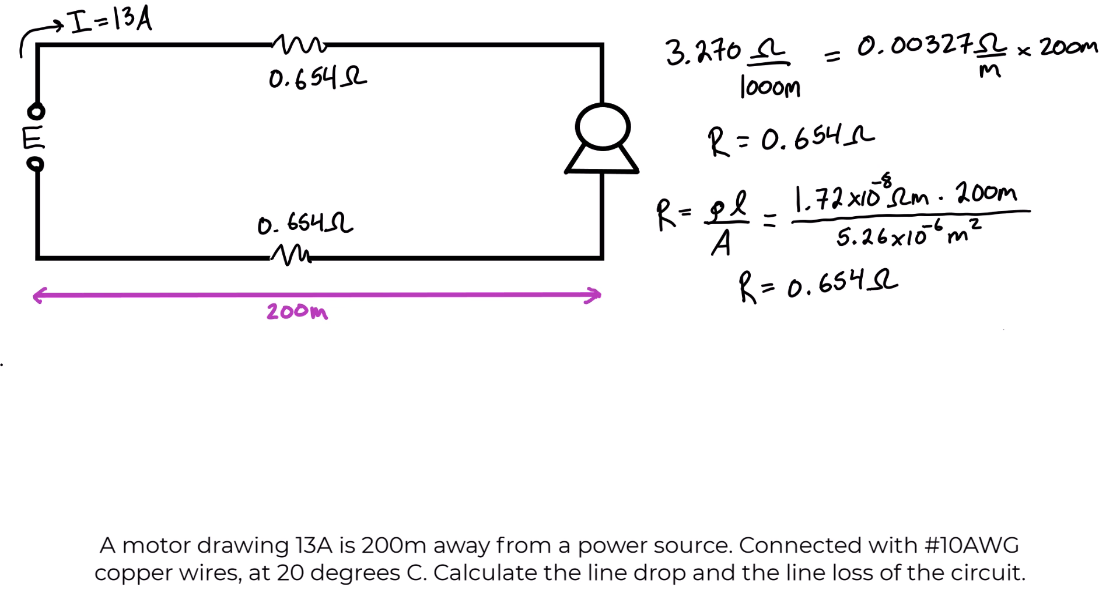Up until this point we've just found the resistance of the conductors. Now the first part of the question was asking us to find the line drop. Line drop refers to voltage—it's actually just asking the voltage drop of the line or of the conductor. So we're just going to apply Ohm's law, V equals IR. We have the current, it was given to us in the problem—it's 13 amps—and the resistance we found for each line is 0.654 ohms, and that's just 8.5 volts.